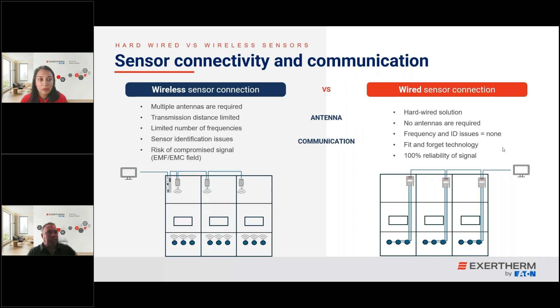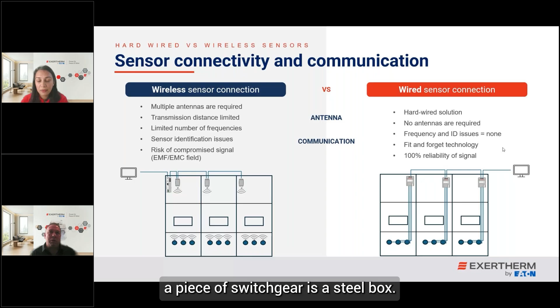And that does beg the question, what are you actually saving? You've got a very short transmission distance. The reason being, as we all know with our mobile phones, you're on a phone call, you get into a lift, an elevator, call it what we wish, the doors close, and you lose that signal because a piece of switchgear is a steel box, an enclosure within an enclosure. So those antennas need to be close by.